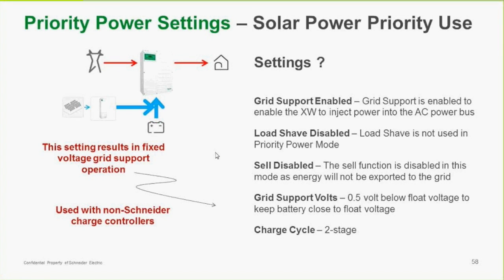Solar power priority use. So in this case, we have grid support enabled. We have load shave disabled. We're not actually pulling anything necessarily from the grid. We're not selling to the grid, and so again, we set our grid support volts, and we use everything we can from the solar panels and the charge controller to power the loads.